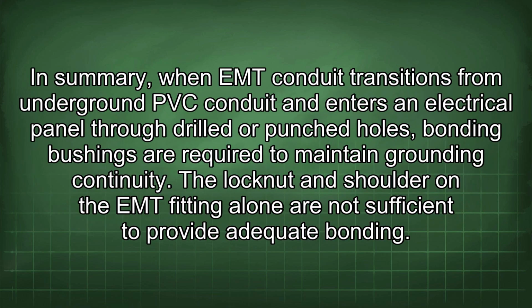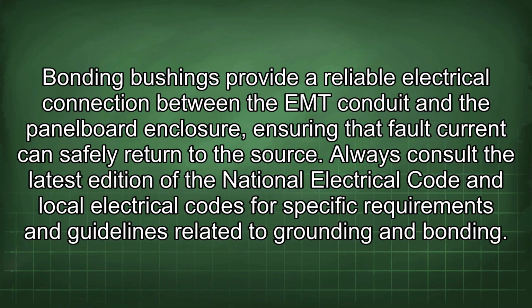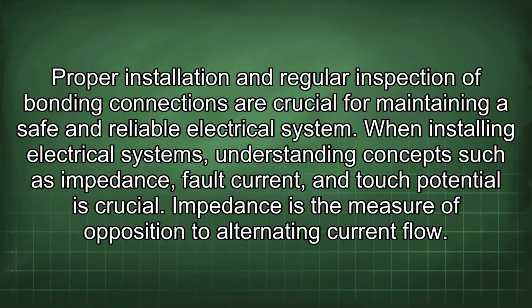In summary, when EMT conduit transitions from underground PVC conduit and enters an electrical panel through drilled or punched holes, bonding bushings are required to maintain grounding continuity. The lock nut and shoulder on the EMT fitting alone are not sufficient to provide adequate bonding. Bonding bushings provide a reliable electrical connection between the EMT conduit and the panel board enclosure, ensuring that fault current can safely return to the source. Always consult the latest edition of the National Electrical Code and local electrical codes for specific requirements and guidelines related to grounding and bonding.